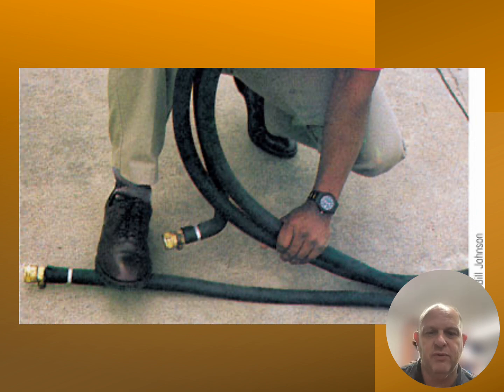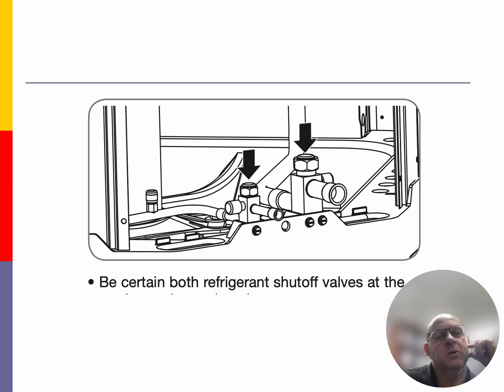So a lot of these slides are very self-explanatory. So be certain both valves, both refrigerant valves on the outdoor unit are shut off at the service ports themselves.